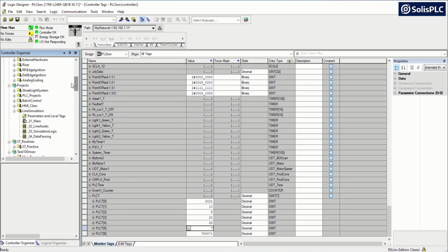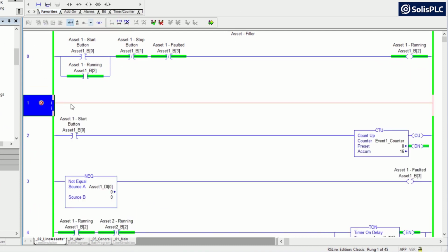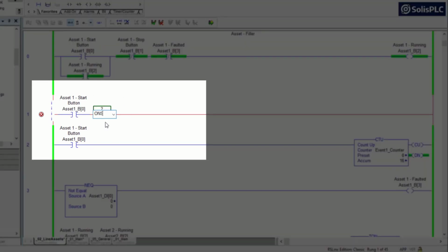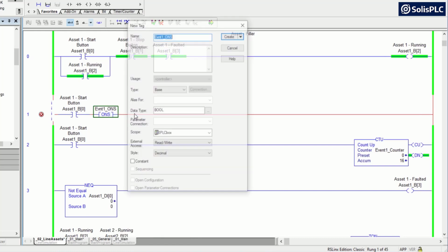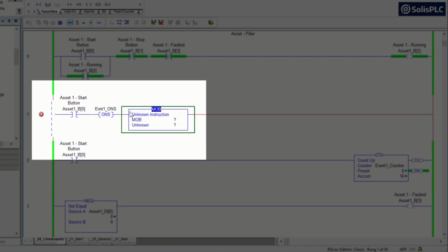Here we can try and capture something a little bit more interesting. So I'm going to create the start push button once again, post that right there. I'm also going to do a one shot, so I don't want this to be continuously spamming my data register, but instead it's going to only happen once. Event 1 underscore one shot. And this is going to be a Boolean on the PLC side. That's perfectly fine. So when this happens, I want to record all those parameters that I've created in my register into an instance for event one. And we're going to do that using move instructions.